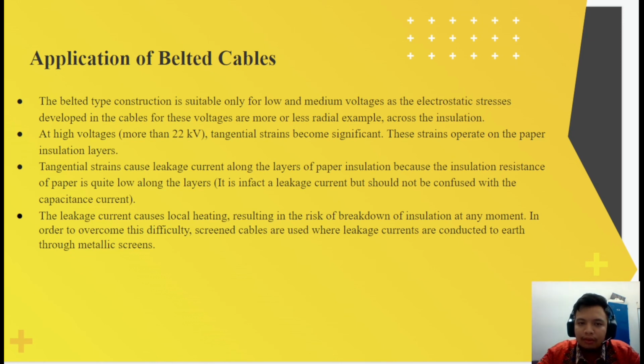Second, at high voltage, more than 22 kV, tangential stresses become significant. The stresses operate on the paper insulation layer. Next, tangential stresses cause leakage current along the layer of paper insulation because the insulation resistance of paper is quite low along the layer. It is in fact a leakage current but should not be confused with the capacitance current. Lastly, the leakage current causes local heating, resulting in the risk of breakdown of insulation at any moment.